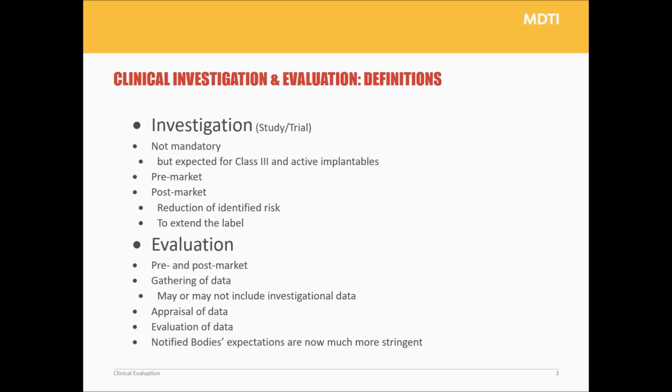So it's less usual to do a post-market study, but if additional risks appear from your post-market surveillance, then you may wish to consider doing a post-market investigation. And also mostly post-market investigations are undertaken to extend a label. So you might be extending the intended use, you might be extending the population to which the device is used.